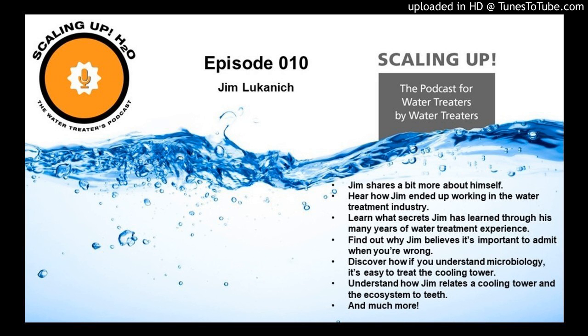He went to work doing some water treatment consulting and called me because they were using some Buckman materials, called me for a formula that used a chrome tracer, because back in the day you could still use chrome in cooling towers, and chrome made a pretty good tracer. Well, the problem was, because I didn't know, and we didn't let it stability test for a long enough period of time, that we added the hexavalent chrome to the formula. It was an acrylate AMP phosphonate, if that tells you anything.